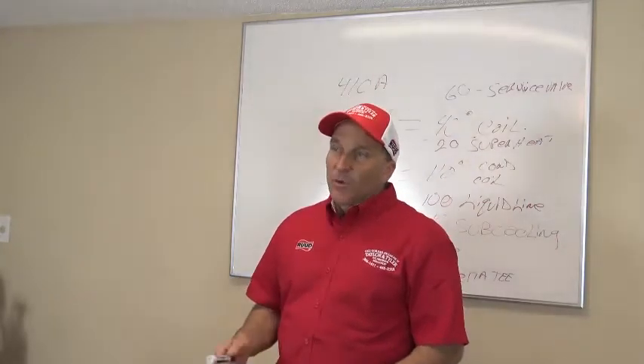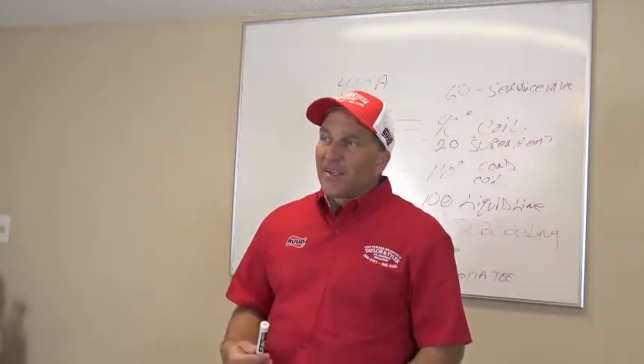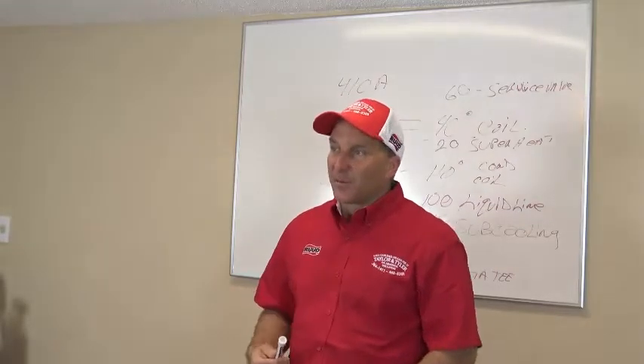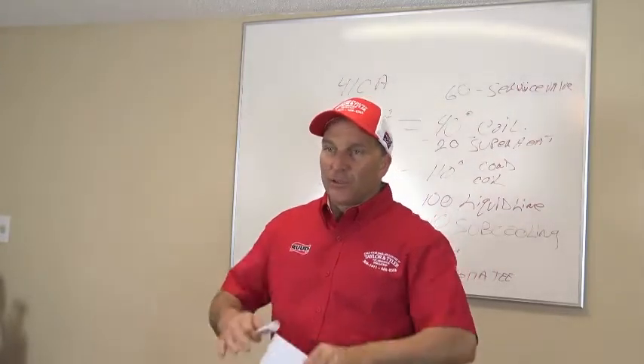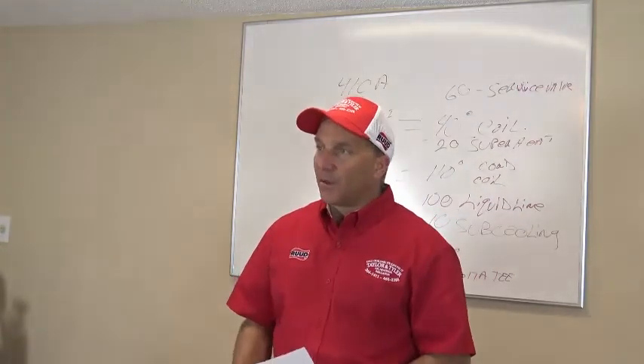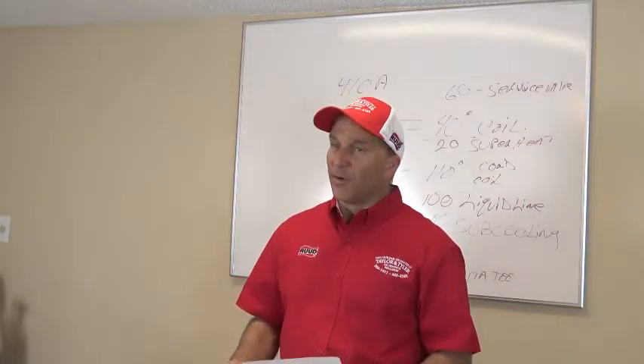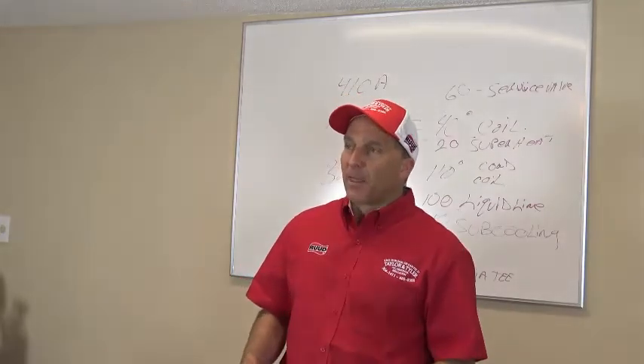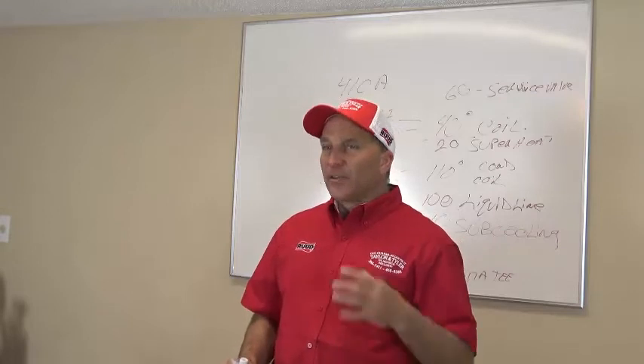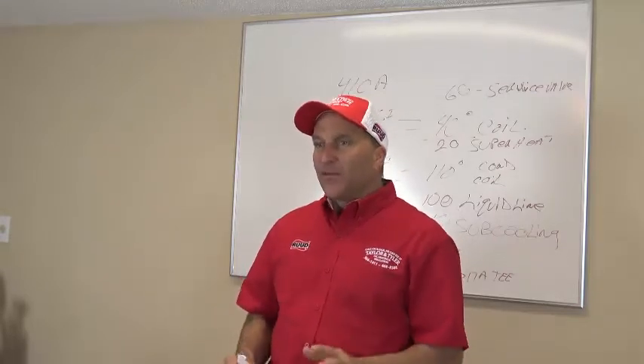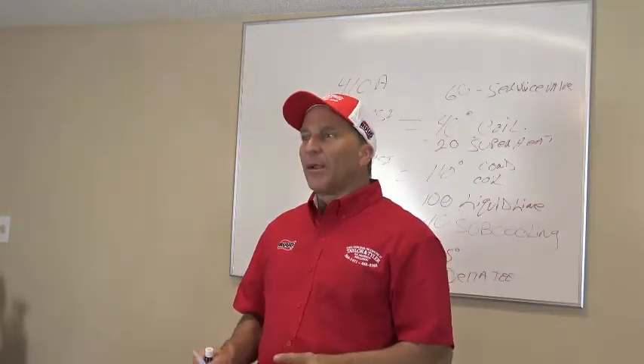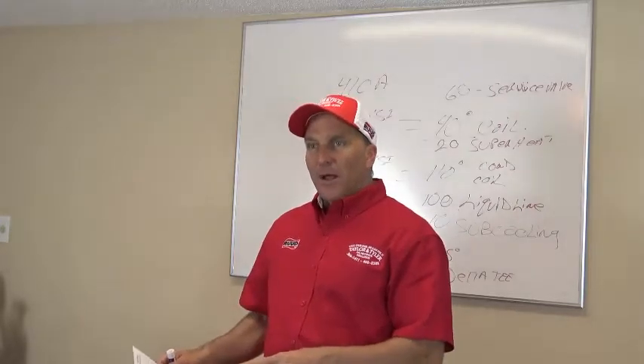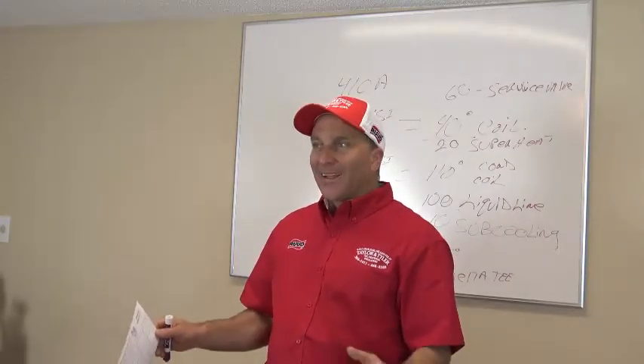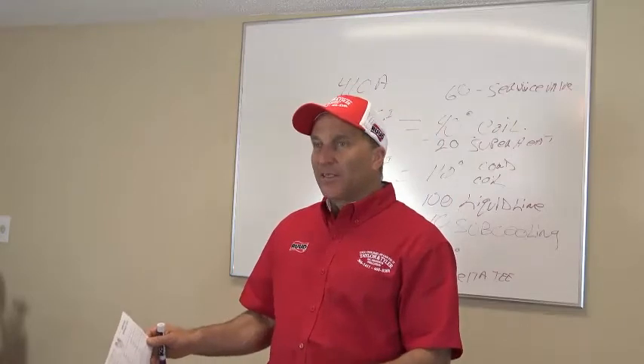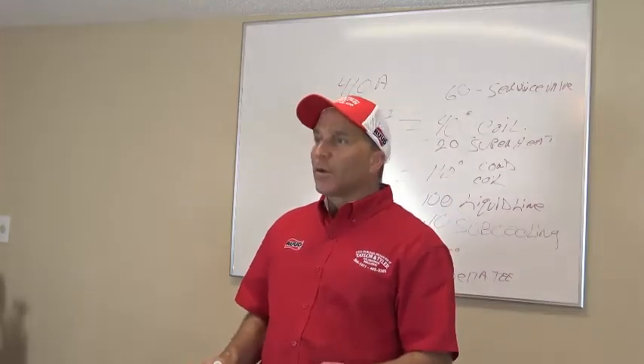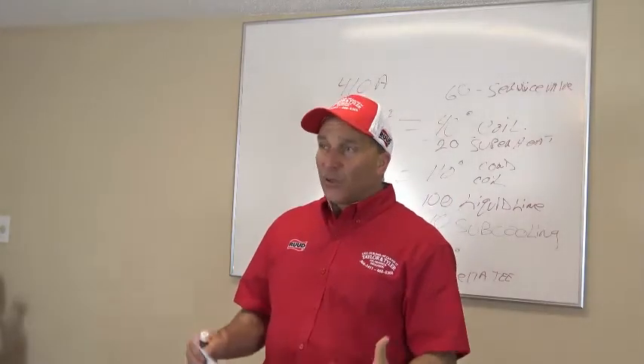So anytime you clean a filthy, dirty condenser, you have got to tell that customer, after you've cleaned it and you checked everything, you're fixing it, ready to leave, you go, look, I just want to let you know, this could happen. When we clean condensers that are that dirty, it is very possible for the bearings to go out in the motor. Now, it's working right now, so I'm not telling you it's bad right now, and I'm not going to replace it if it's not bad. It's working right now, but I will tell you, you've seen that condenser.